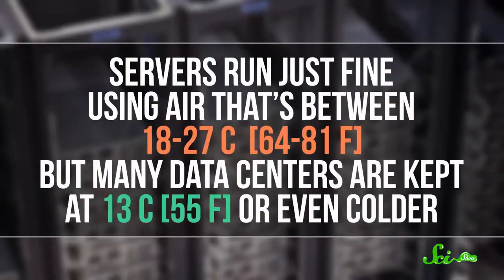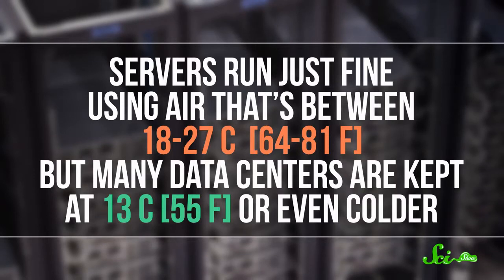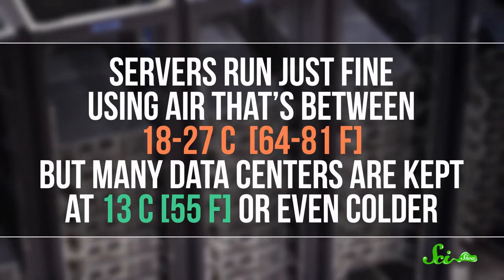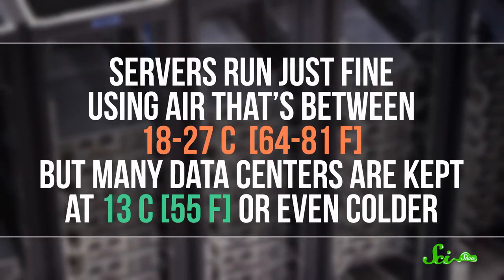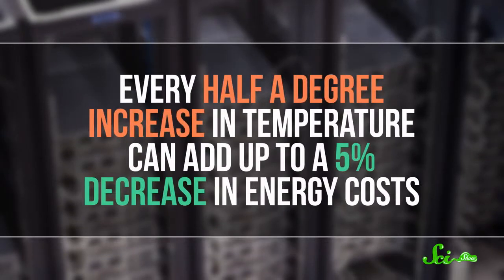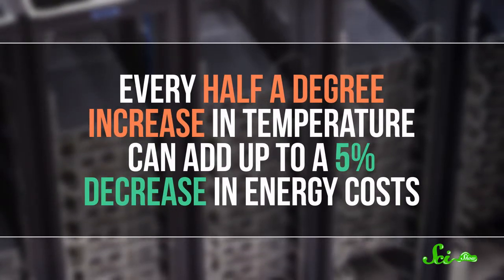You can also cut the amount of electricity air conditioning uses by actually raising the temperature. Servers run just fine using air that's between 18 and 27 degrees, but many data centers are kept at 13 degrees or even colder. Every half a degree increase in temperature can add up to a 5% decrease in energy costs. So while a 27-degree room might be a little toasty for some people, there's no reason we can't just raise the temperature in the room and save a lot of energy.